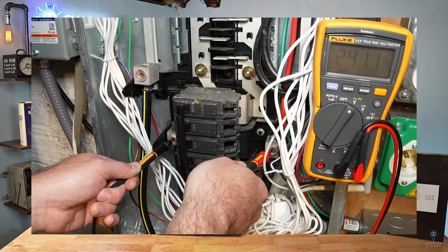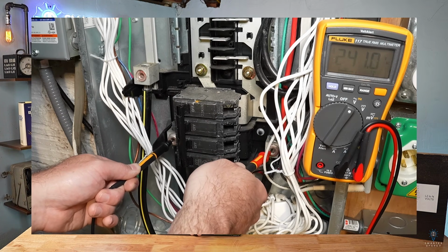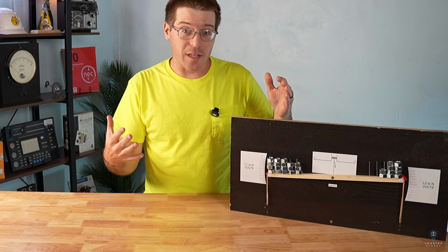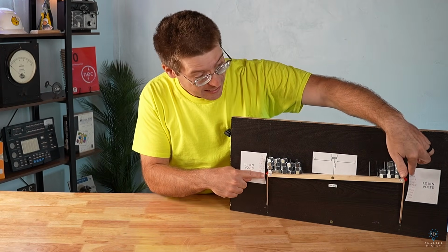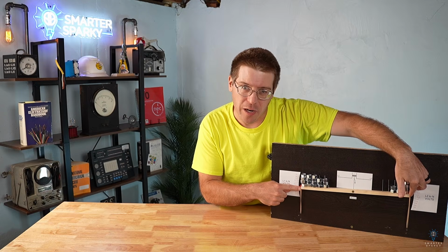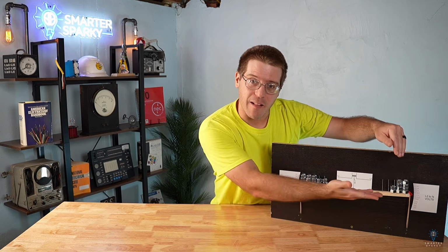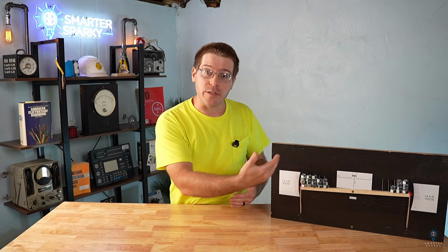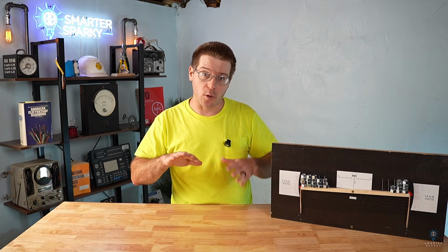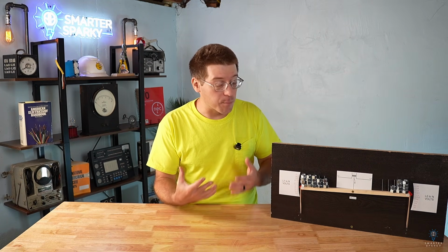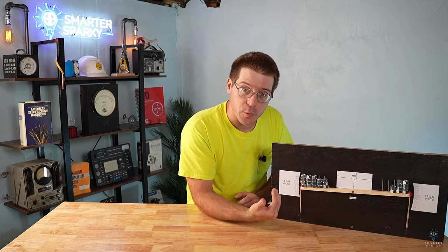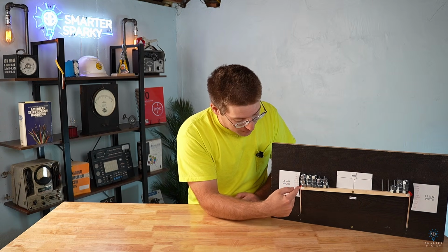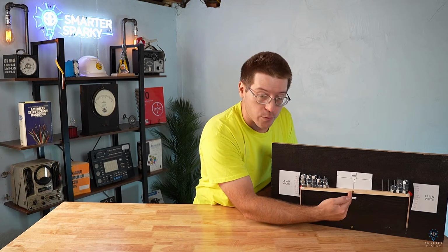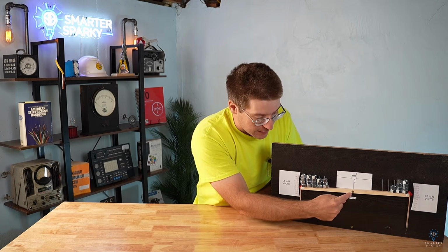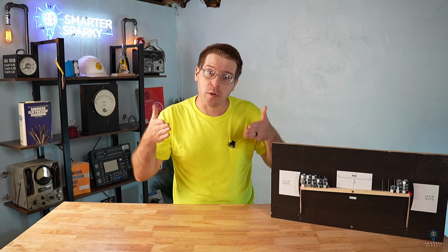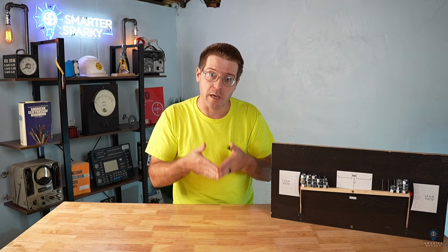When we measured the line-to-line voltage, we did not observe any crazy voltage swings. That told us the incoming line voltage was stable from line to line. That's why we were only visualizing it here as a solid beam. When we measured either line to neutral, that's where we started to see those voltage fluctuations. That implied the problem was at the common point between those two measurements. And if we were to measure line 1 to neutral and line 2 to neutral, the common measurement point is that neutral connection. That's what narrowed us down to the neutral being the problem here.